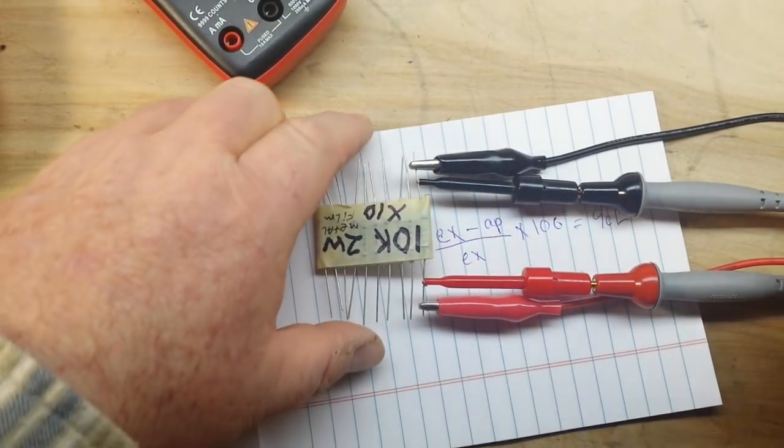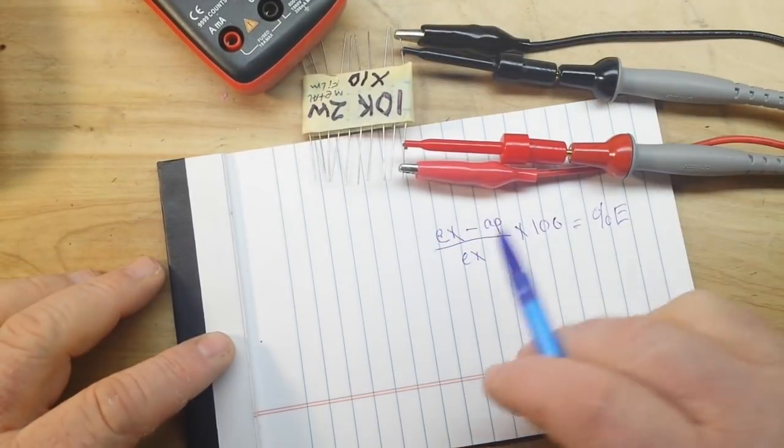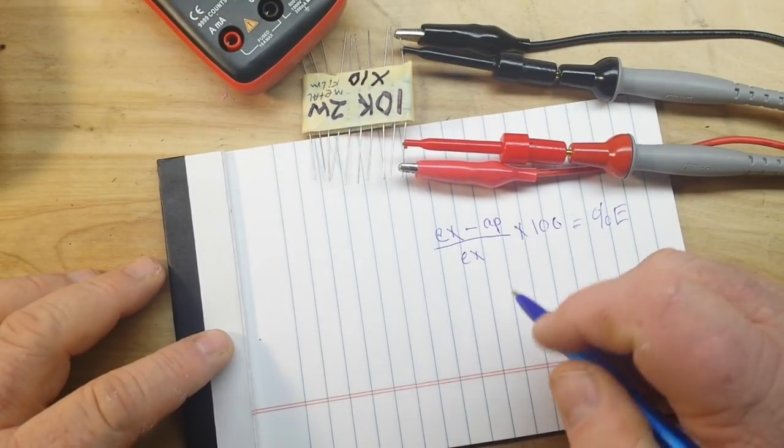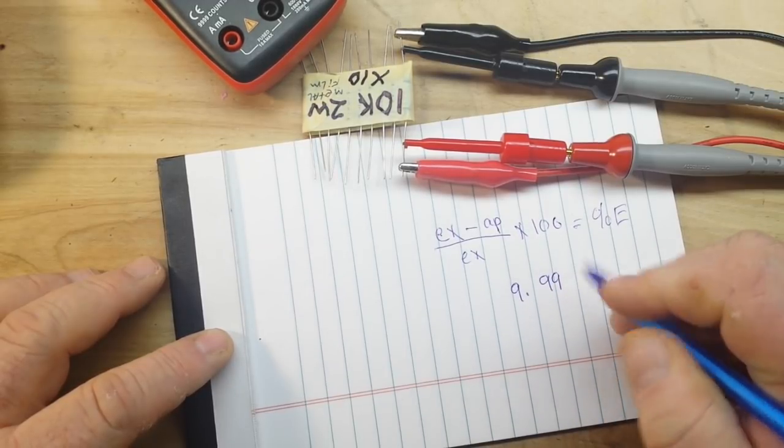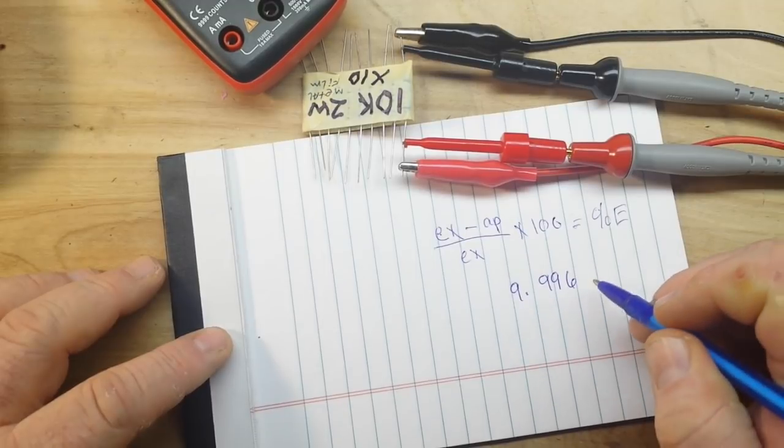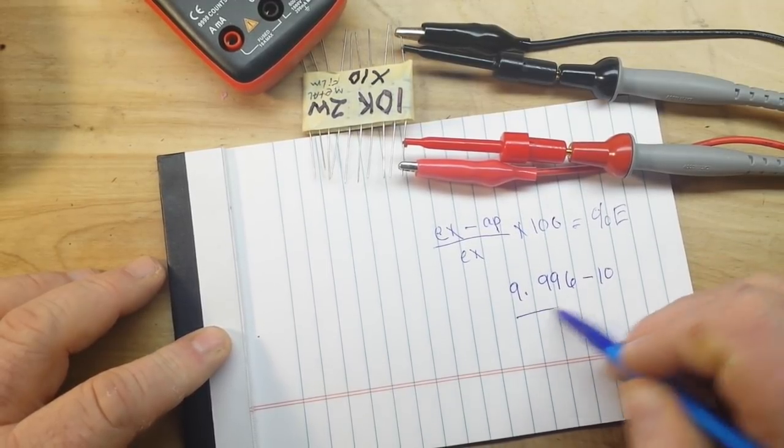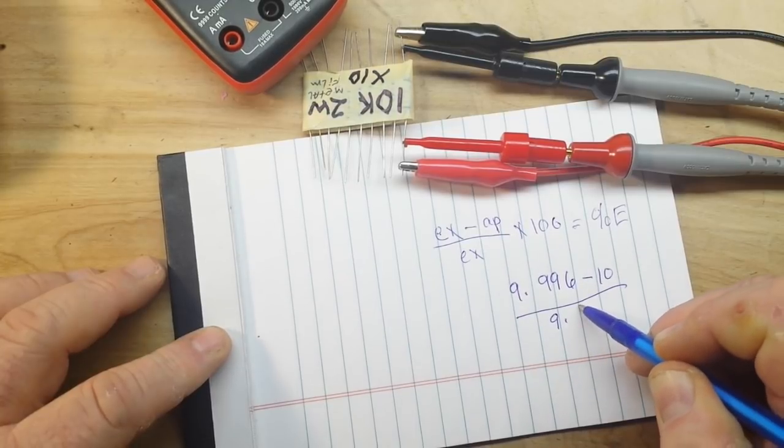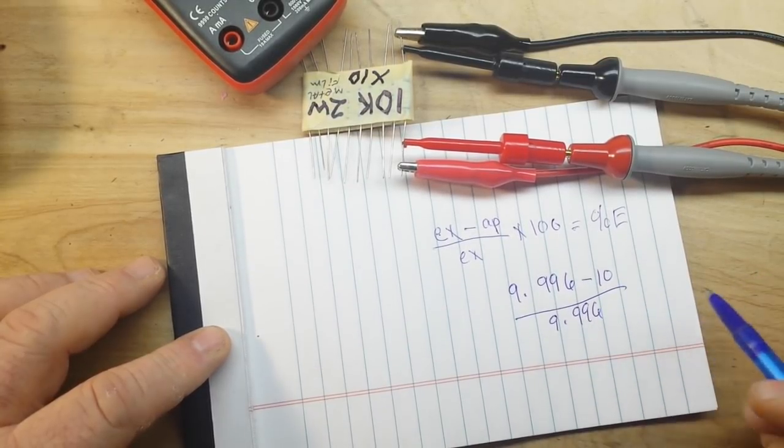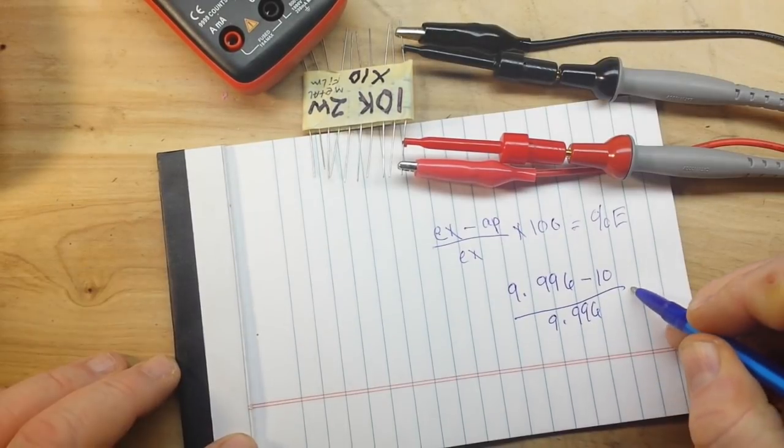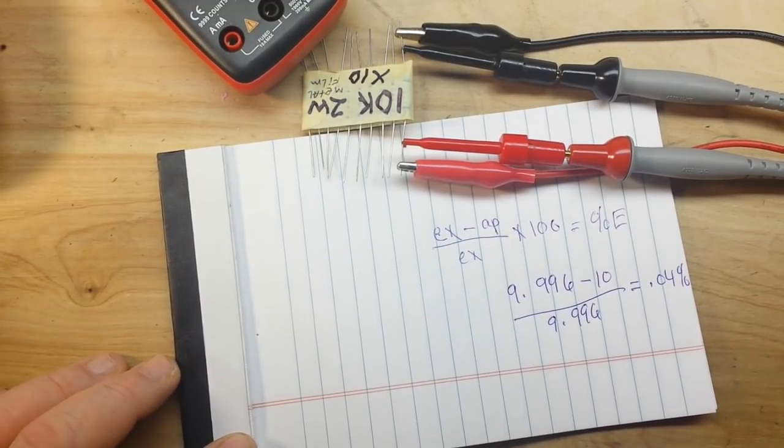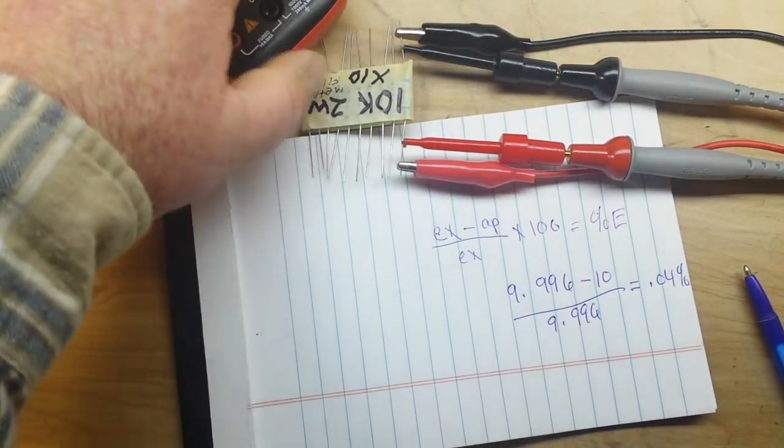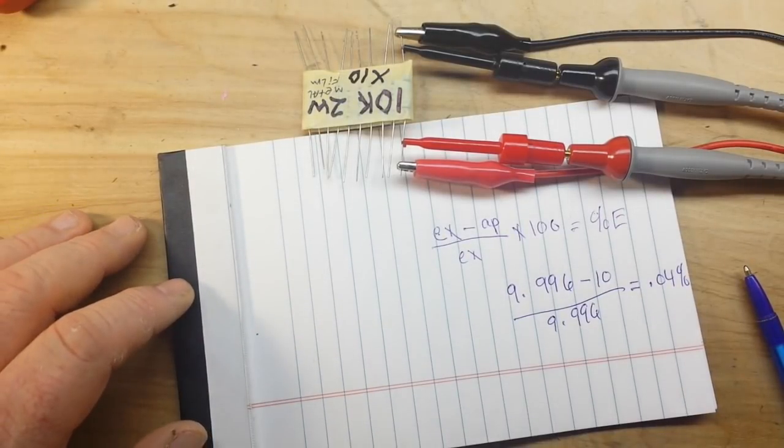If we take the reading from our Fluke and apply what we have here, so we say 9.996, which is where we're at right now, minus 10 over 9.996, and do the math, we get our answer: 0.04%. So that's well within spec of the 0.05. So I think we have a trustworthy enough reading.